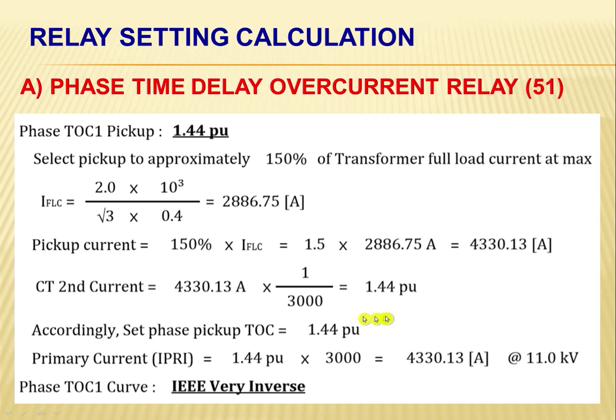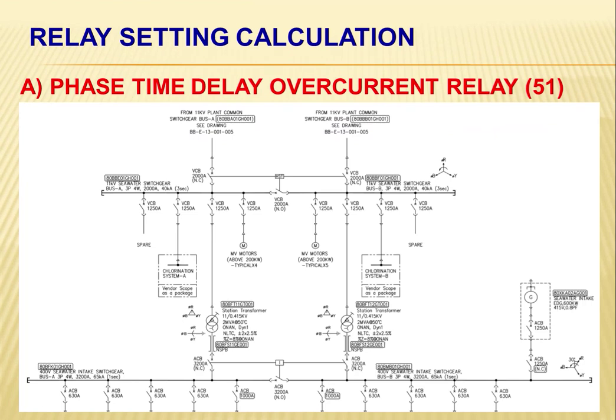Okay, so that's why we have this value. The set phase pickup TOC is 1.44 per unit. Okay, so our phase time over current curve, we will be adopting the IEEE very inverse. Okay, so next, this will be our coordination time interval, CTI. We'll be using this one later to compute our TDM.